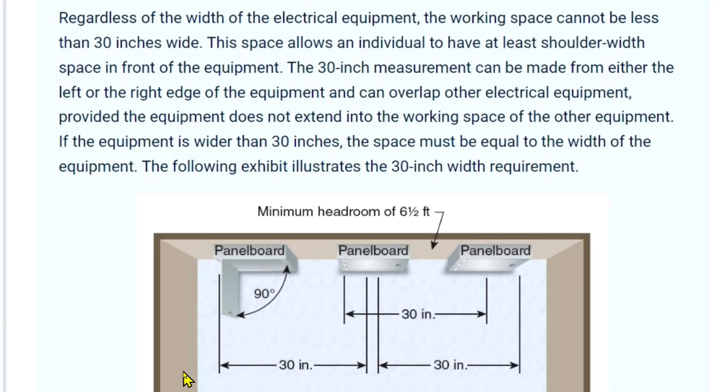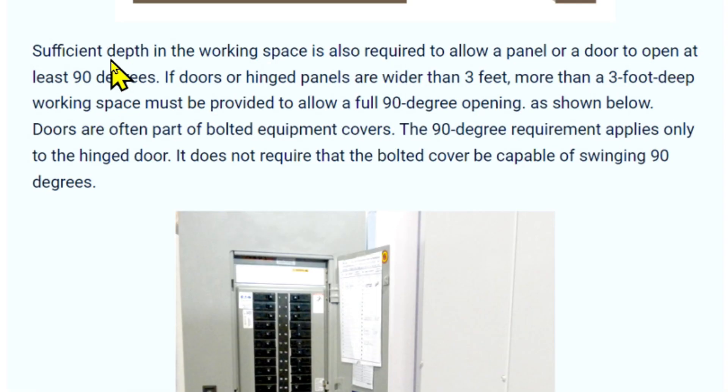So here you have a panel board and it has to have 30 inches. The door must be able to open 90 degrees. Now this could overlap under this panel board, and this could be 30 inches, and then this needs to be 30 inches. And then minimum headroom of 6 and a half feet.